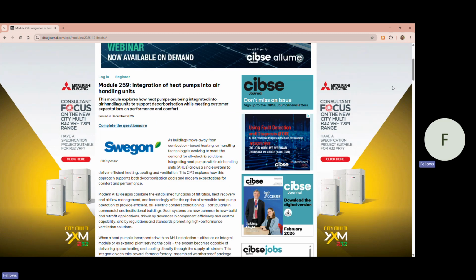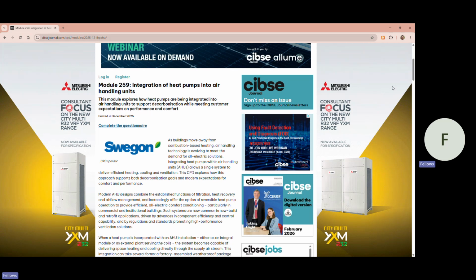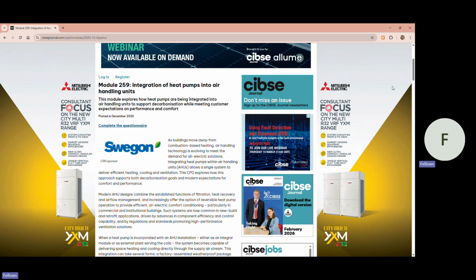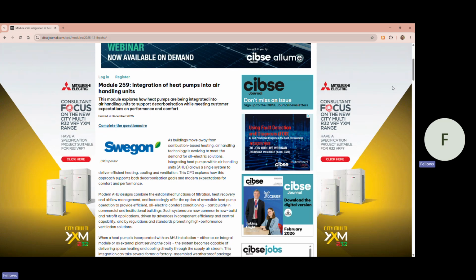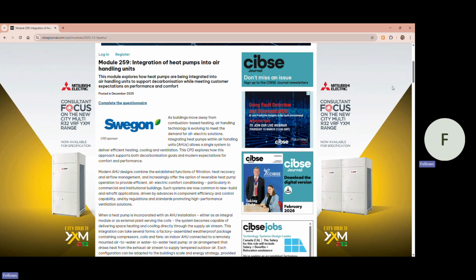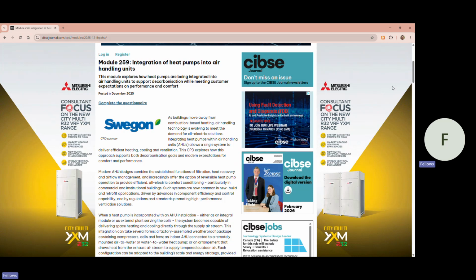As buildings move away from combustion-based heating, air handling technology is evolving to meet the demand for all-electric solutions. Integrating heat pumps within air handling units, or AHUs, allows a single system to deliver efficient heating, cooling, and ventilation. This CPD explores how this approach supports both decarbonisation goals and modern expectations for comfort and performance.